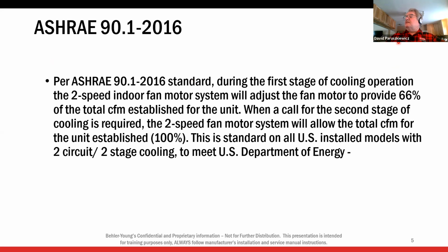So what the 2-speed is doing is your circulation fan. When G is energized by itself, we're going to have 66% full speed. When we go to Y2, cooling stage 2, or a heating call, we're going to go to full speed, which is 100%. So again, the G call, the circulation fan is 66% full speed, and then the second stage cooling or heating call will be full speed at 100%. This is going to be the case on everything over 5 tons, including air handlers.